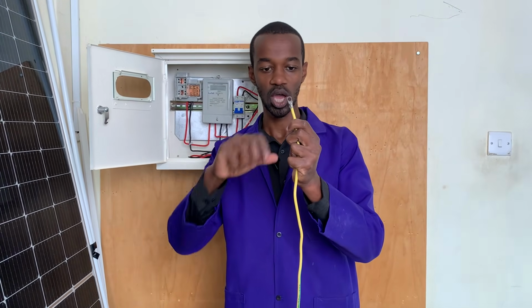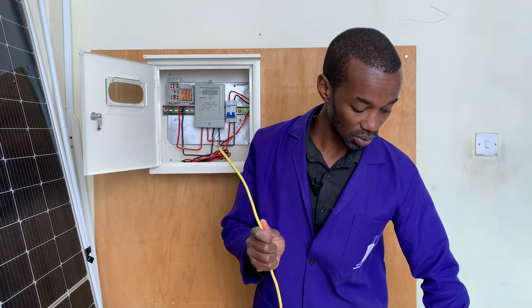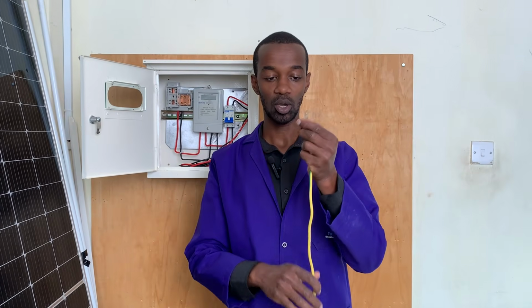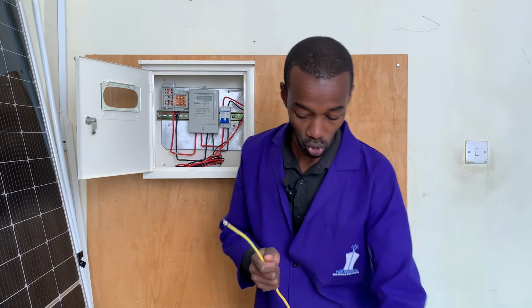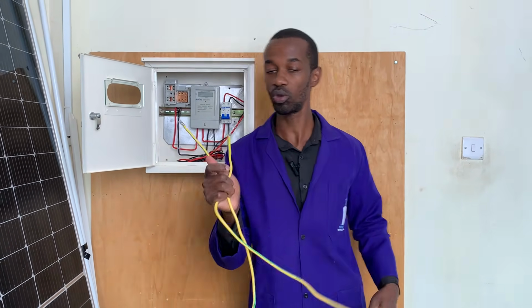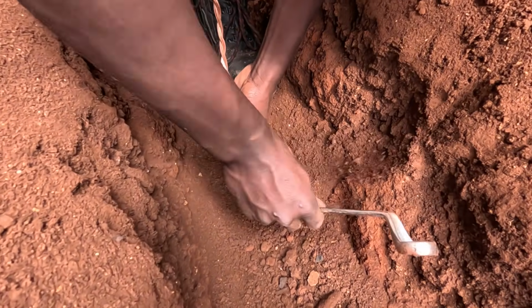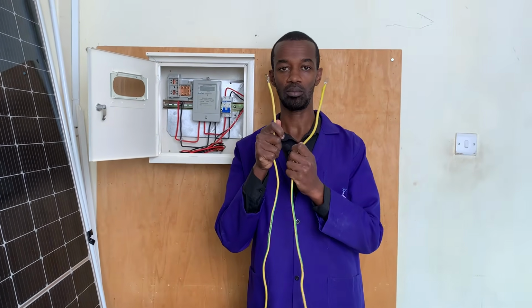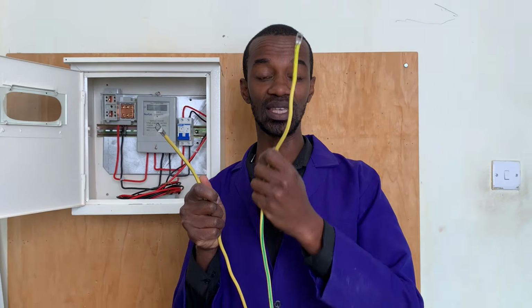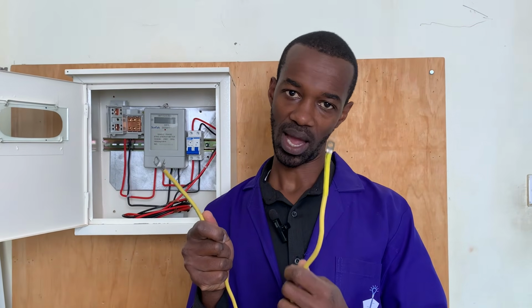So from the meter box, we will have this cable, separate from the neutral. From the consumer unit, which is this one, it will be connected here, and we will also have a separate cable going all the way to the earth rod. So at the meter box, we have only two cables: one going to the meter box, and one going all the way to the earth rod.